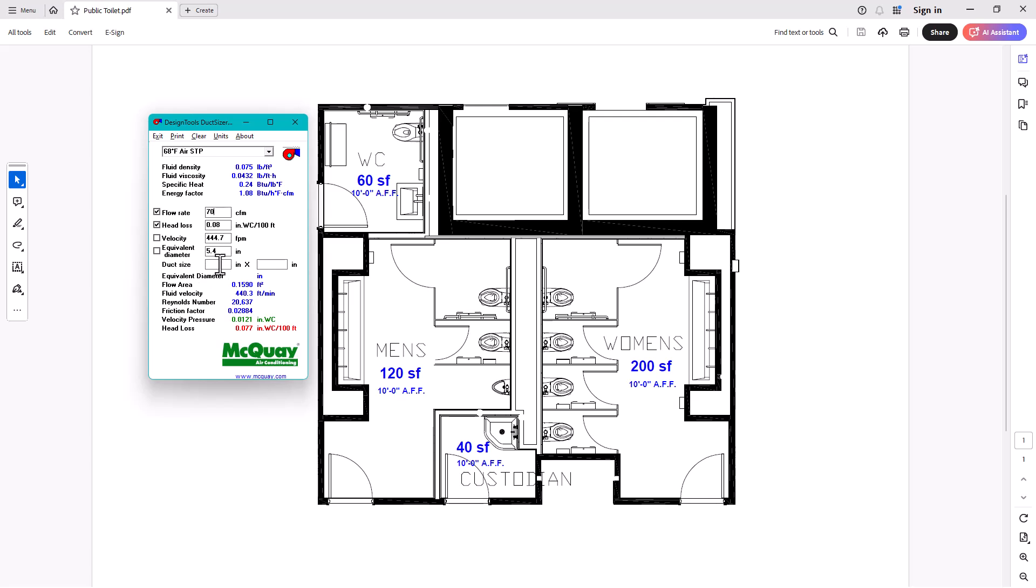So if it's low pressure, let's go here and say my 70 CFM that I wanted. And again, you can do in here clear units. And again, we can do 70 CFM friction, 0.08, 70 CFM. And then that's all you need. And you need to put your duct size. What's going to be your input? Usually my input is the height. Why? Because that's the determined factor of, I usually put a height, say, I start with 10 of height, because usually the architect doesn't want to give us so much space on the ceiling plenum. So you can put either 8. The minimum is going to be 6. But since this is a very small CFM, we can put 6. The height will be 6. Let's put 6. There we go. So it says my duct size is going to be 6 by 4.